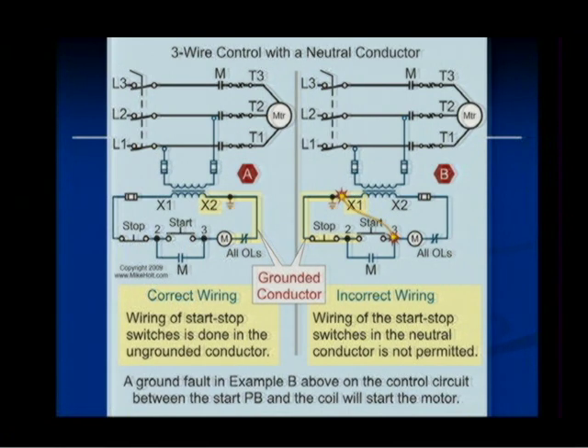Now, the code actually says that you cannot use a neutral conductor for any kind of control. And the reason being is because if we connected a hot wire to one side of the coil, and then we use a neutral conductor to the other side for the control, if there was a short of the neutral conductor to one of the other wires, you could bypass all the safety protection of a 3-wire control circuit, and then, of course, the coil could be energized, the motor could run.